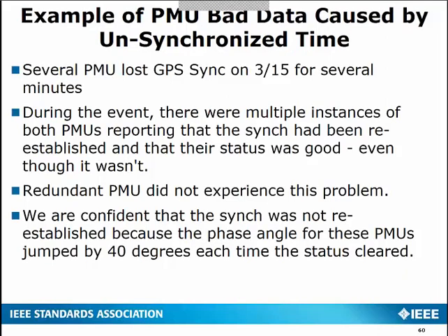Another example of unsynchronized time occurred when a clock receiver, again another clock receiver issue, lost GPS sync in March of 2015. During the event, there were multiple instances of multiple PMUs reporting that the sync was good, had been reestablished, and the status was good. So the clock was incorrectly saying, I have good data, meaning the end device just trusted that data. Now, a redundant system did not experience this problem.